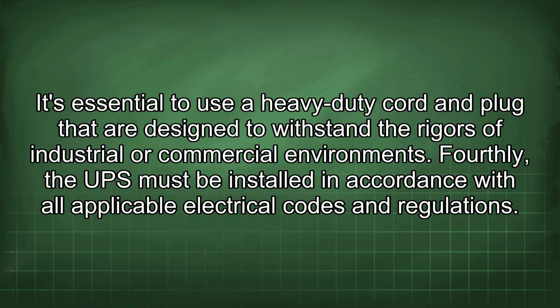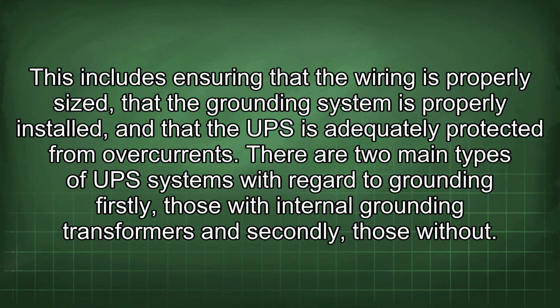Fourthly, the UPS must be installed in accordance with all applicable electrical codes and regulations. This includes ensuring that the wiring is properly sized, that the grounding system is properly installed, and that the UPS is adequately protected from overcurrents. There are two main types of UPS systems with regard to grounding. Firstly, those with internal grounding transformers, and secondly, those without.